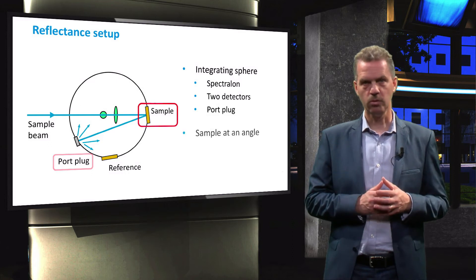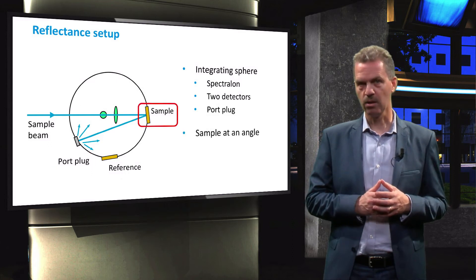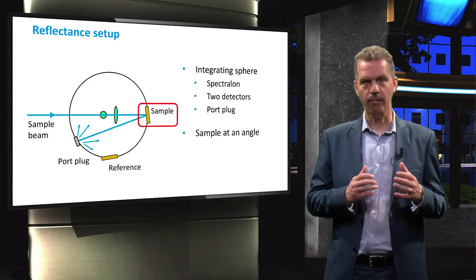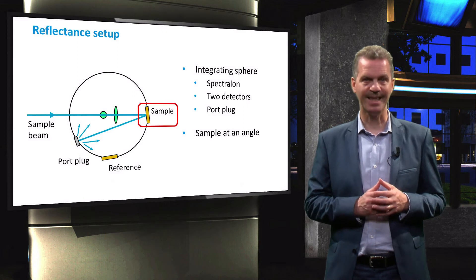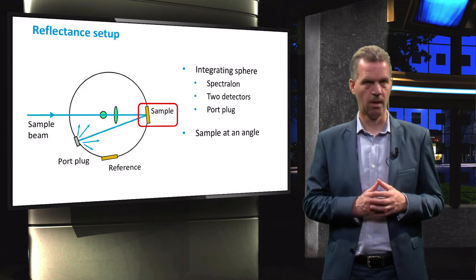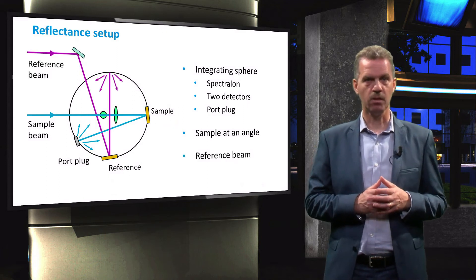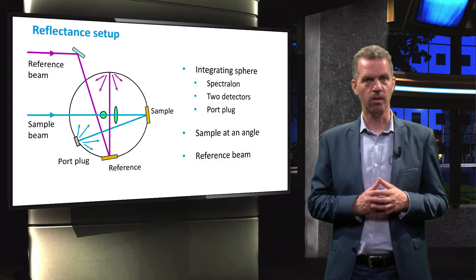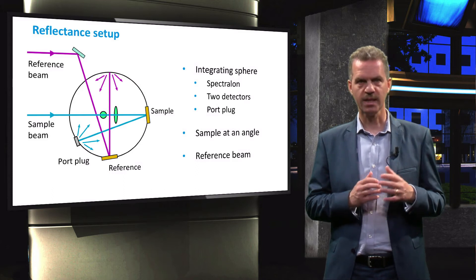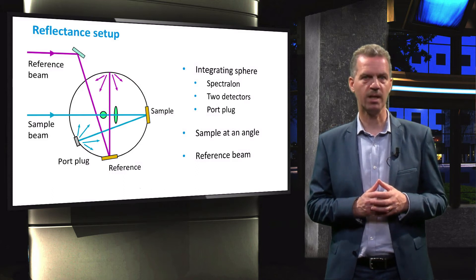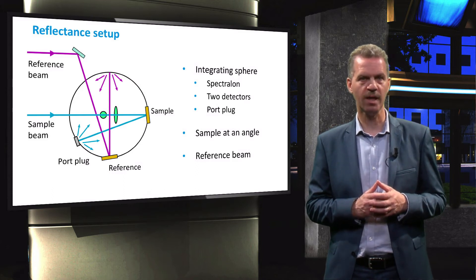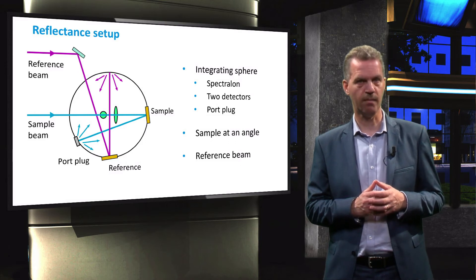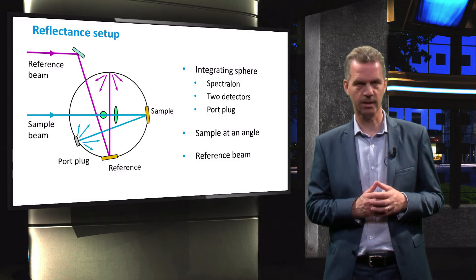In order to direct the specular reflected beam towards the port plug, the sample is placed at an angle. A reference beam can be directed into the sphere by a mirror, such that the reflectance of the chamber can be determined and corrected for when the reflectance of the sample is calculated.